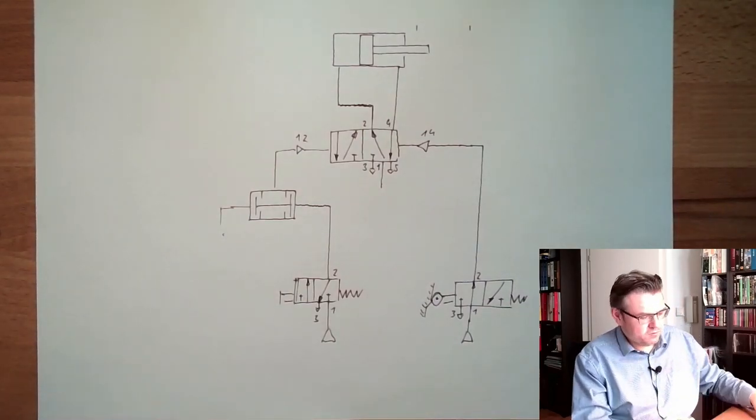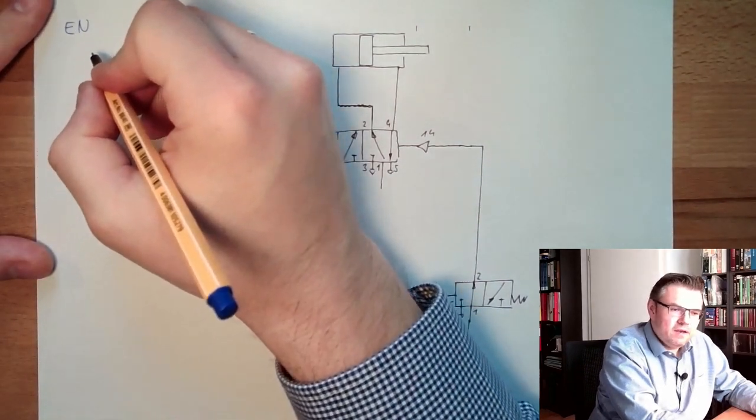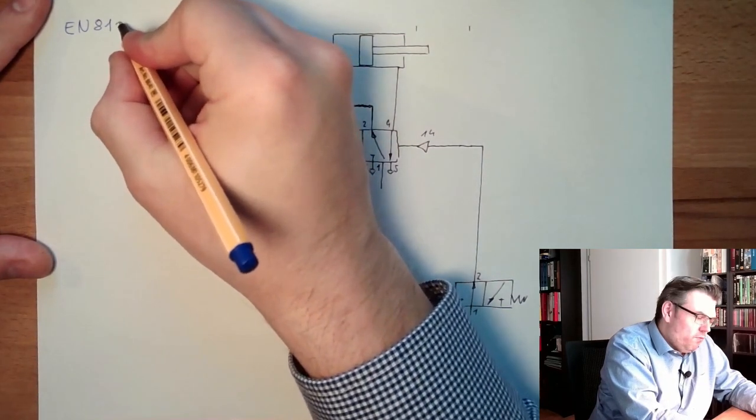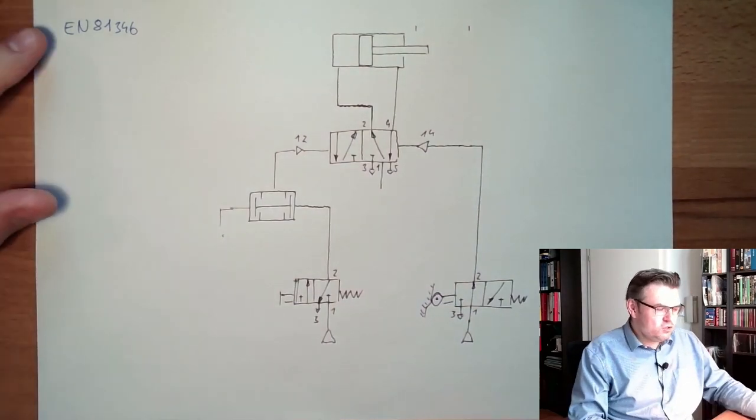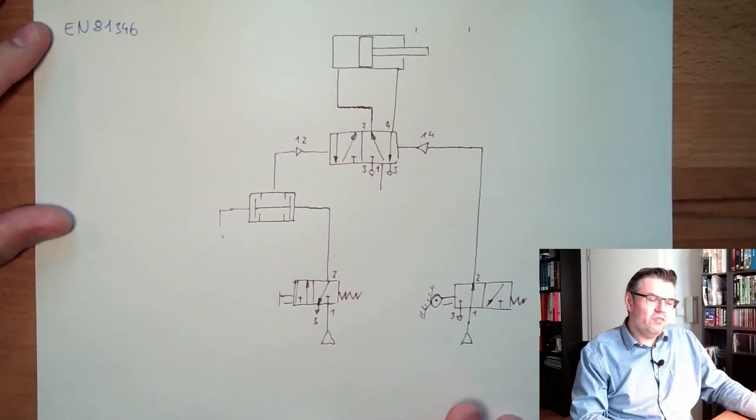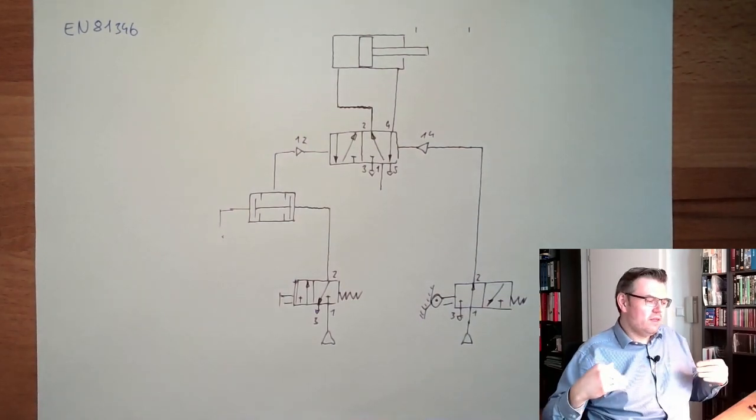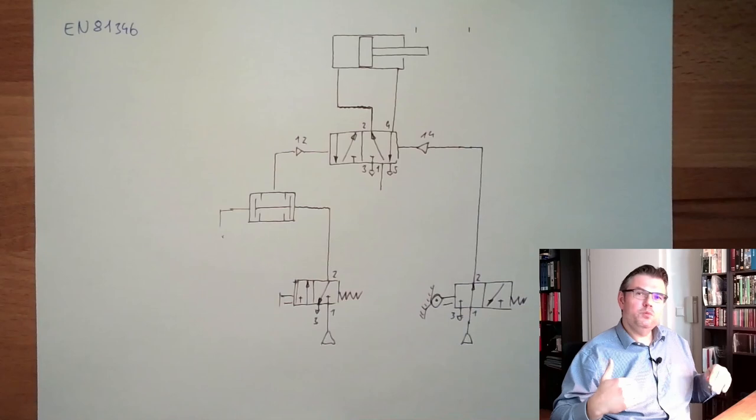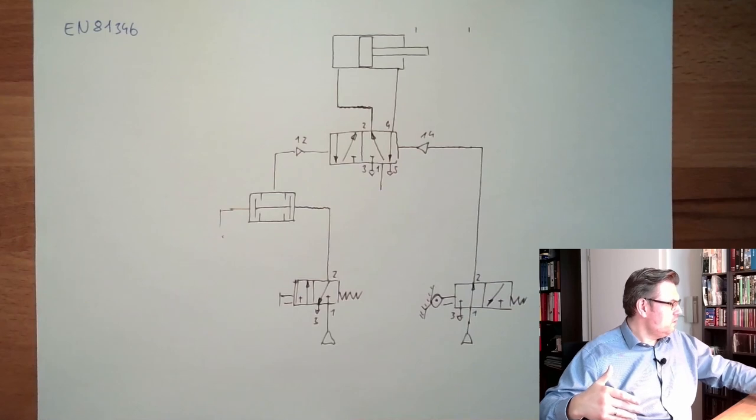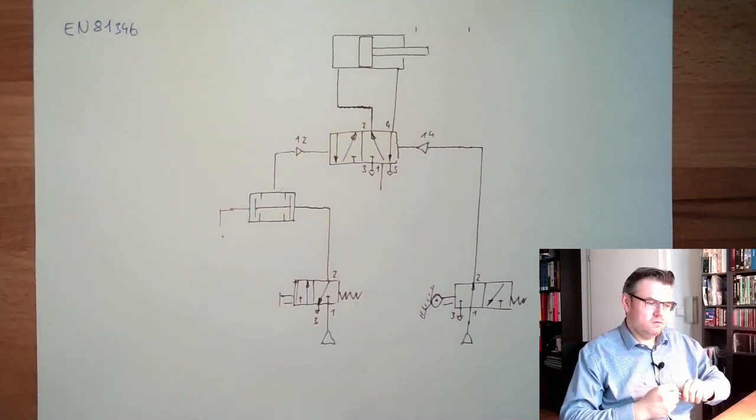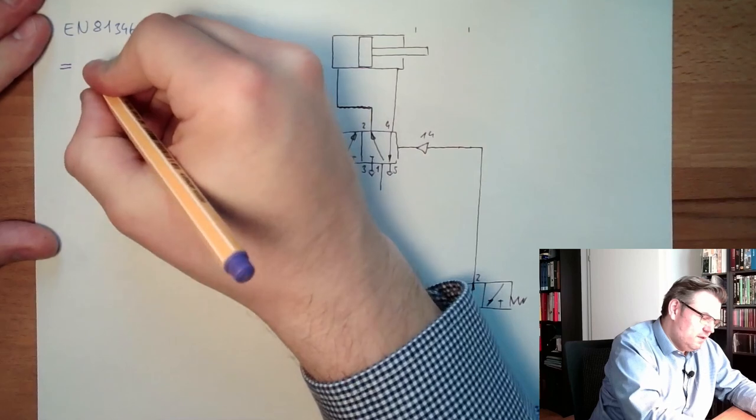There are standards for this. One standard is for instance the European standard EN 81346. This shows how we shall name things. There are several possible aspects under which we can name them. There is the aspect of function. If we want to name them according to function, the prefix of the names is this equal sign. This is a function aspect.